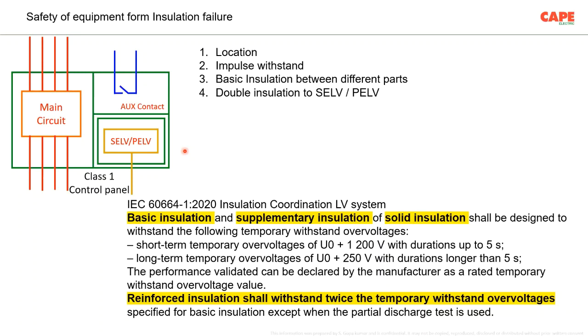Now the standard recommends that the insulation levels between these items, the class 1 part of the equipment and SELV, PELV, for example the basic and the supplementary insulation of the solid insulating material which you are using, must be able to withstand this much voltage, and the manufacturer should declare the value. This is the fact which is included in the standard.